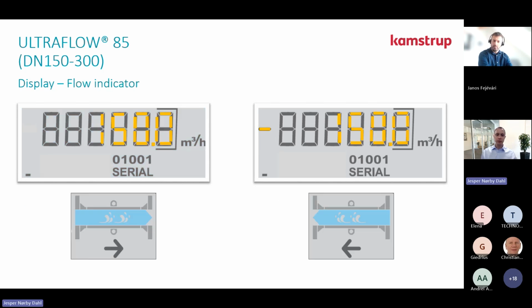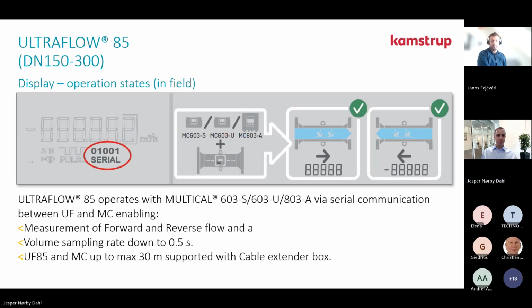Then you can see the actual flow in cubic meters per hour, either forward flow, or, if it's reverse flow, a minus showing you that it is reverse flow. The display can also show if it talks serial communication with the calculator. As I said before, we have these two new PCB types of the Multical 603, the S or the U version, and the 803 updated firmware version. The display will write "serial", telling you that the ULTRAFLOW 85 is working in serial connection with the calculator.